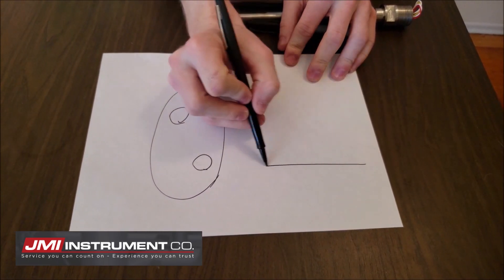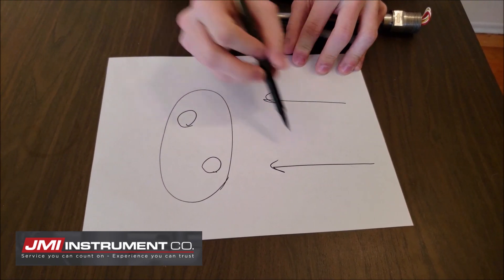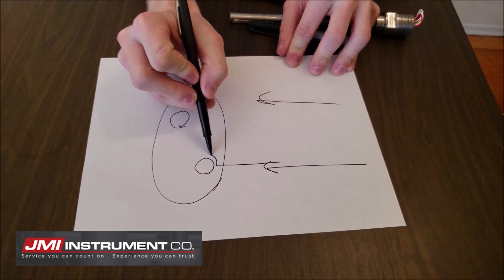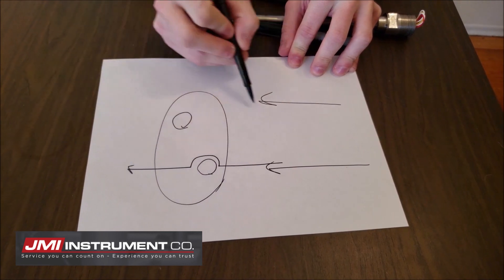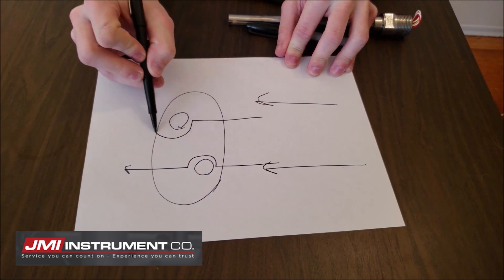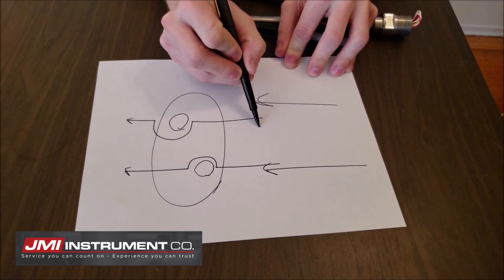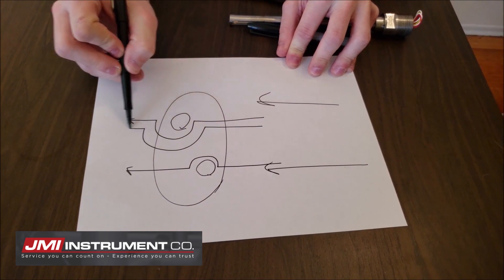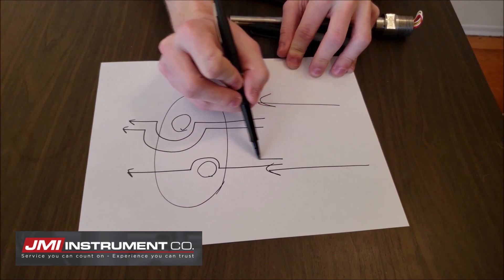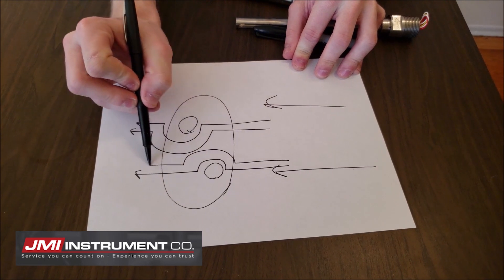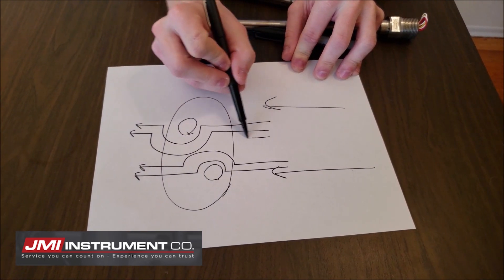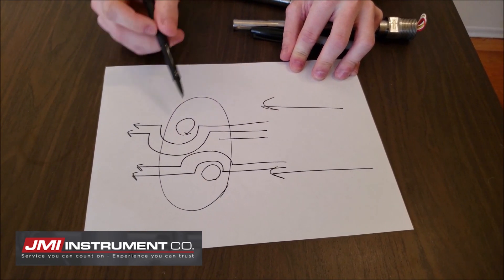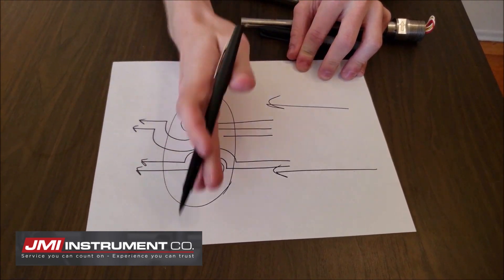Take your same airflow going this direction and watch what happens. It's going to curve around, and the two curves are virtually never going to intersect. This causes for much greater gas flow measurement stability with the probes being offset as opposed to in line.